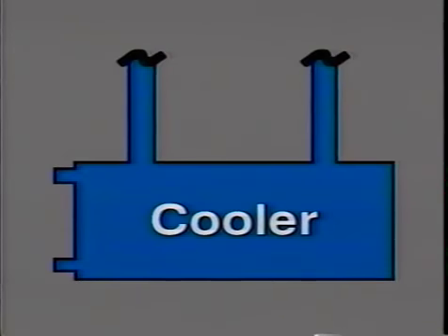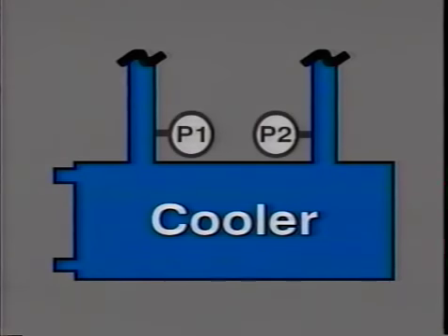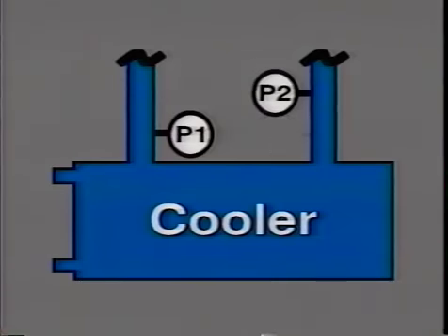Pressure taps for taking pressure readings across the cooler should be as close to the inlet and outlet as possible and at the same height. If there's any difference in the height of the gauges, a correction will have to be made. We'll discuss this in more detail later in the program. Now let's look at the condenser section.